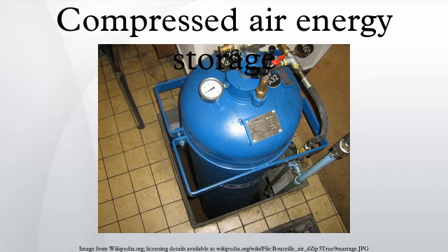Diabatic storage dissipates much of the heat of compression with intercoolers into the atmosphere as waste, essentially wasting the renewable energy used to perform the work of compression. Upon removal from storage, the temperature of this compressed air is the one indicator of the amount of stored energy that remains in this air. Consequently, if the air temperature is low for the energy recovery process, the air must be substantially reheated prior to expansion in the turbine to power a generator.